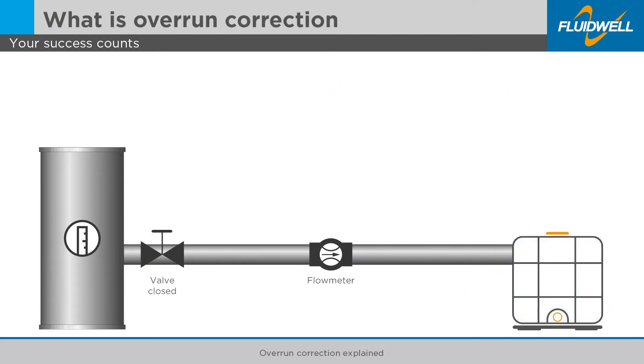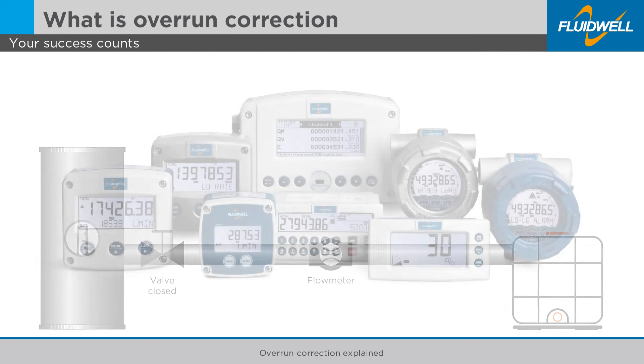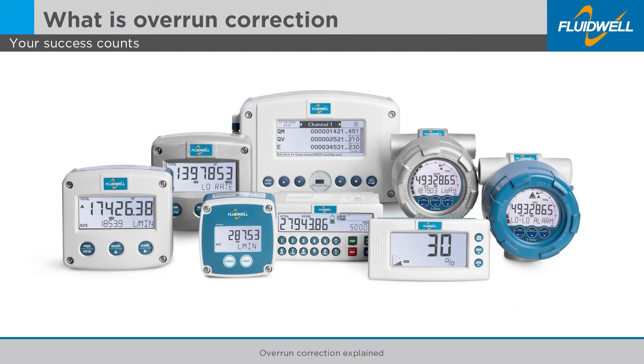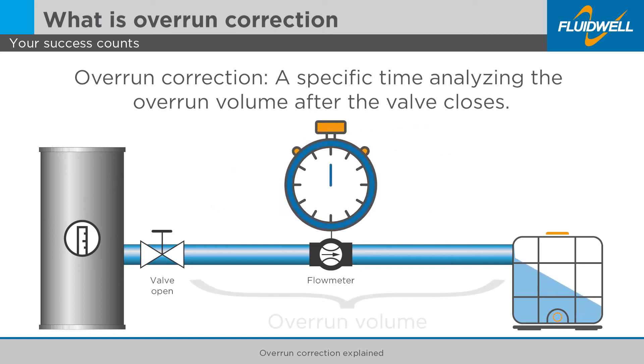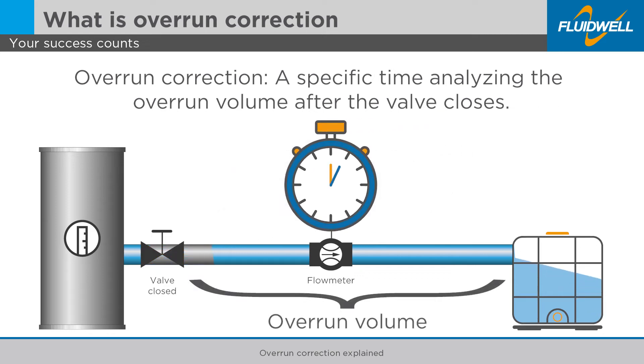What is overrun correction? Fluidwell batch controllers have a self-learning overrun correction. During a specific time set by the operator, the controller analyzes the overrun volume of the batch and automatically corrects the end-of-batch timing of the control outputs.